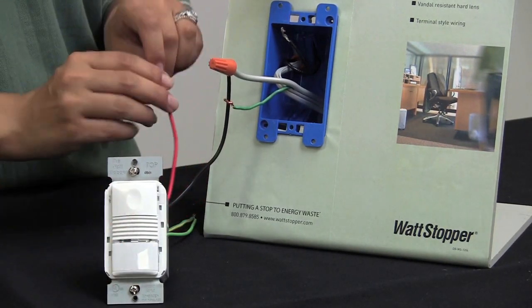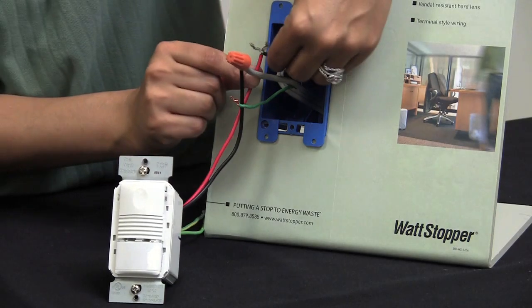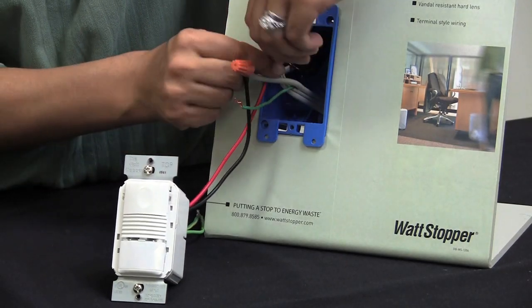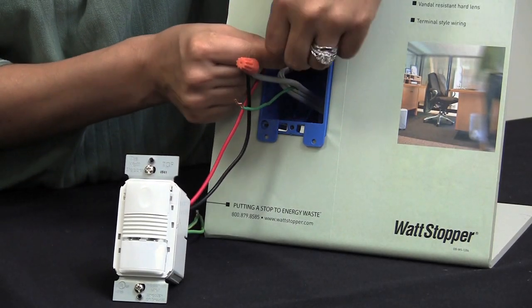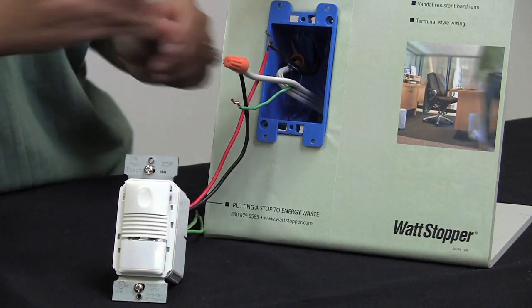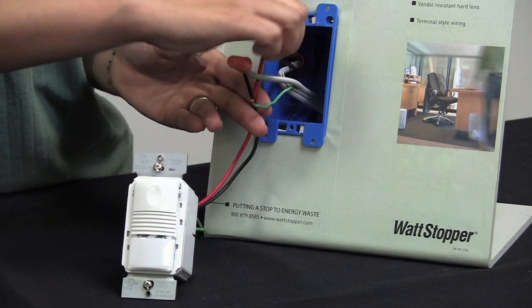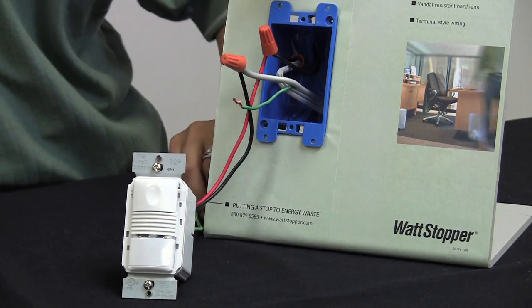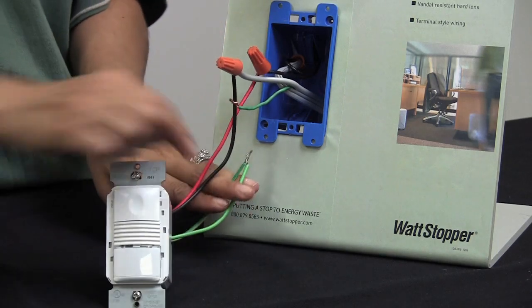Next we will take the red wire from the sensor and wire that to the lighting load. And last we will take the green wire from the sensor and wire that to the ground.